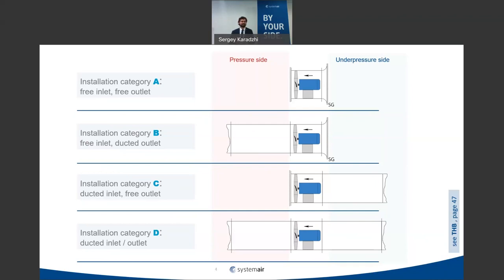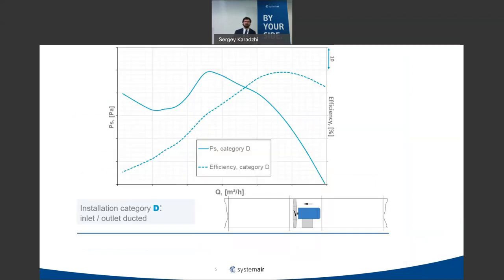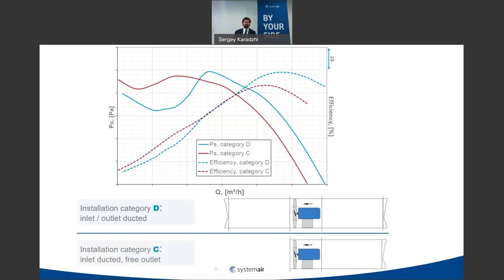A fan can have slightly different curves even when measured on a standardized test rig, depending on the installation category. For example, a fan measured in category D — with duct on inlet and outlet — can show much lower efficiency and a different pressure curve when measured in category C without a duct on the outlet.